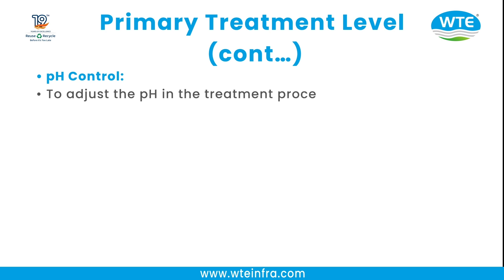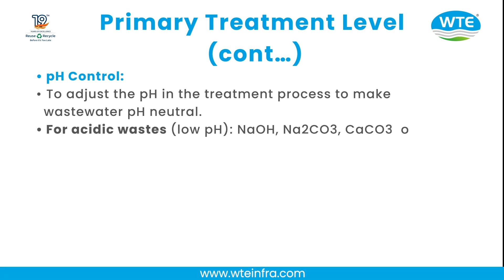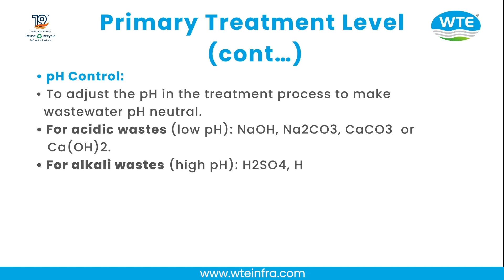pH Control: To adjust the pH in the treatment process and make the wastewater pH neutral. For acidic waste (low pH), chemicals such as NaOH, Na2CO3, CaCO3, or Ca(OH)2 are used. For alkaline waste (high pH), H2SO4 or HCl are used.